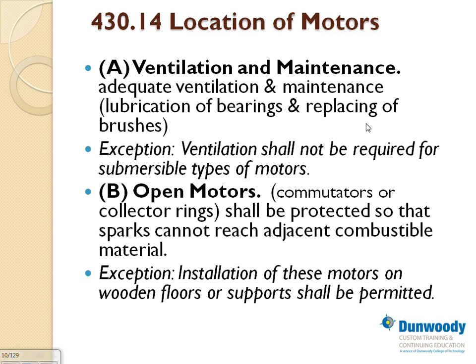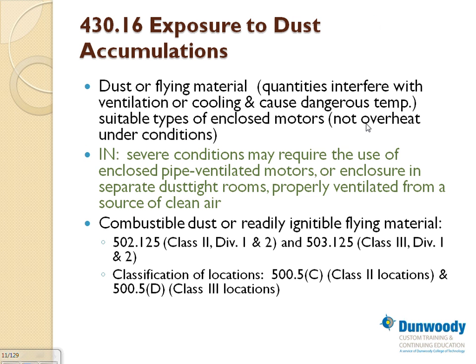Okay. HVAC equipment, which is a major part of the motors, is for the most part induction motors. Exposure to dust and accumulations. You need to take care of your equipment. If the dust is going to interfere with the operation of the equipment and make them overheat, you have to clean them. And you have to have a suitable type of enclosures for them.